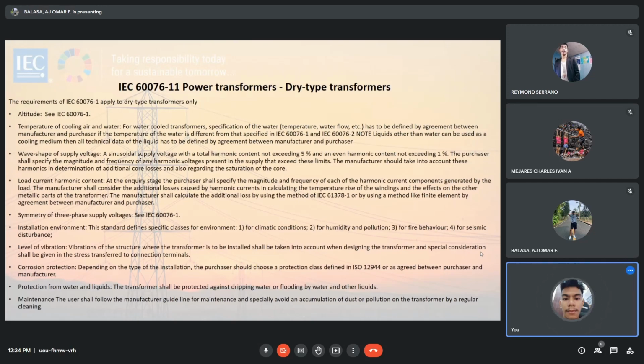Corrosion protection. Depending on the type of the installation, the purchaser should choose a protection class defined in ISO. So, ibang ibang standard pero ina-apply din siya dito. ISO 12944 or as agreed between sa purchaser na naman tsaka sa manufacturer. Protection from water and liquids. The transformer shall be protected against dripping water or flooding by water and other liquids.